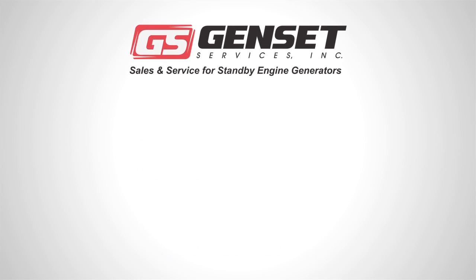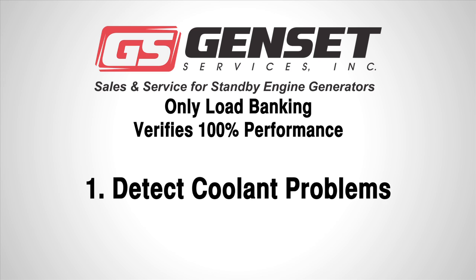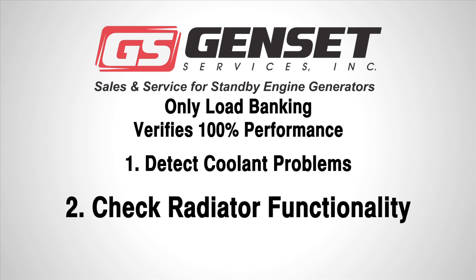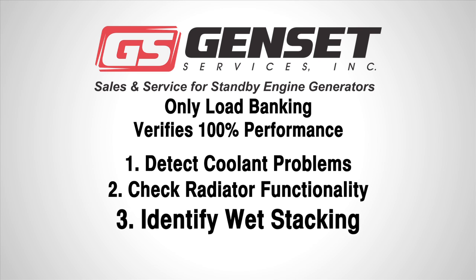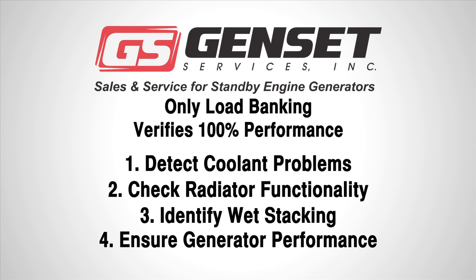So to summarize, load banking to set NFPA standards is the only method to verify 100% performance and will: 1. Detect problems due to coolant, 2. Detect problems due to the radiator, 3. Identify issues connected to light loading that can lead to wet stacking, and 4. Make sure your generator is ready to perform.